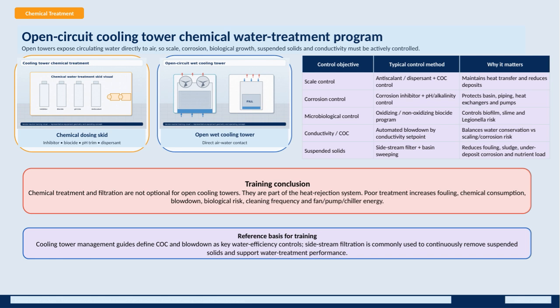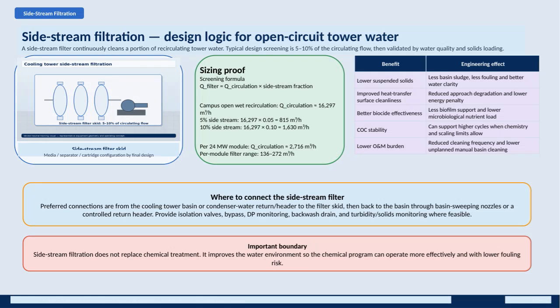This training is based on recognized cooling tower management guides, which emphasize cycles of concentration and blowdown control as key strategies for water efficiency. Side stream filtration is widely used to continuously remove suspended solids, thereby enhancing overall water treatment performance. Let's talk about side stream filtration and its role in open circuit cooling tower water systems.